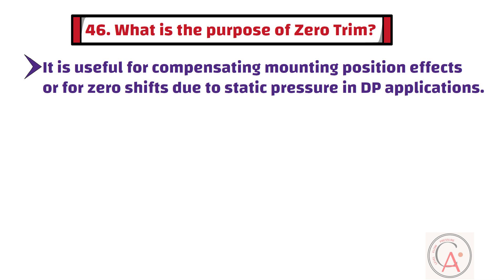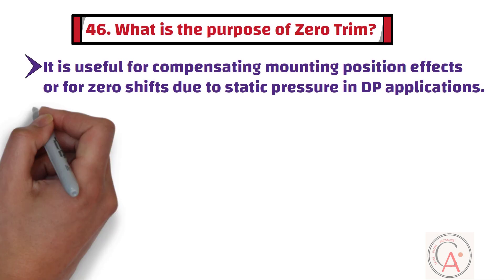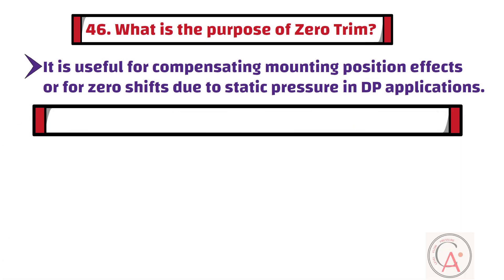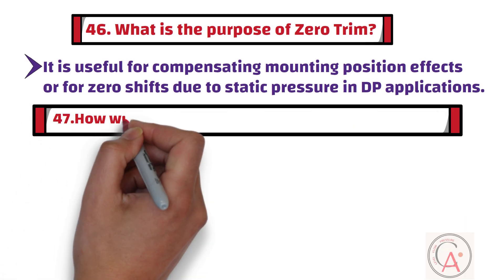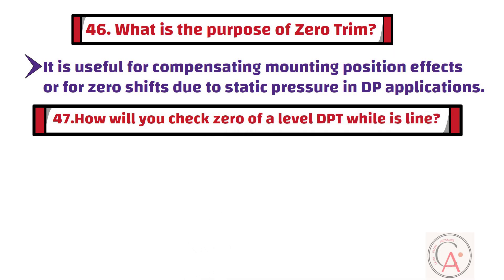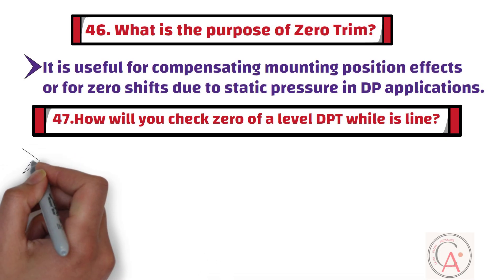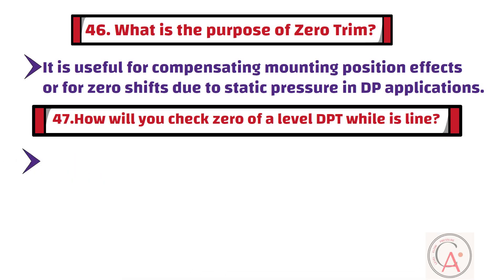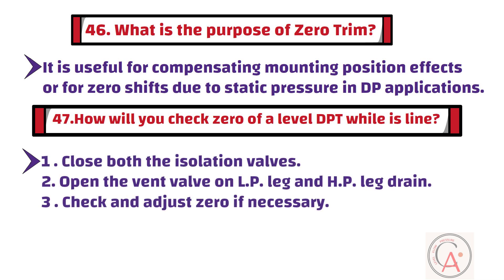Question 47: How will you check zero of a level DP transmitter while it is in line? To check the zero of the DP transmitter, first close both the isolation valves. Then open the vent valve on the LP leg and HP leg drain. Finally, check and adjust zero if necessary.